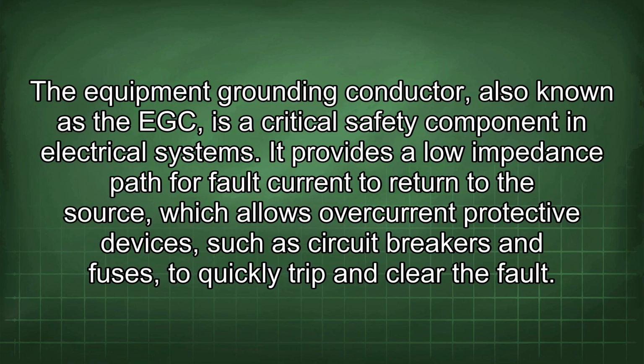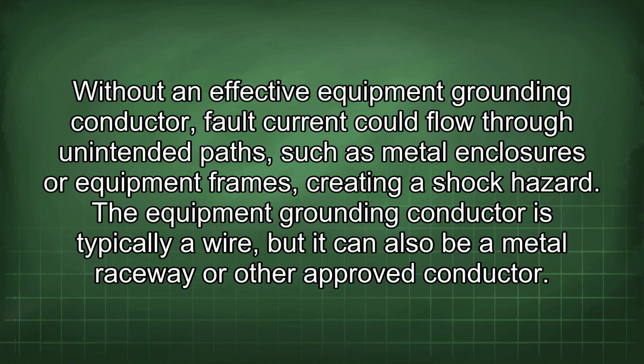The equipment grounding conductor, also known as the EGC, is a critical safety component in electrical systems. It provides a low impedance path for fault current to return to the source, which allows overcurrent protective devices, such as circuit breakers and fuses, to quickly trip and clear the fault. Without an effective equipment grounding conductor, fault current could flow through unintended paths, such as metal enclosures or equipment frames, creating a shock hazard.